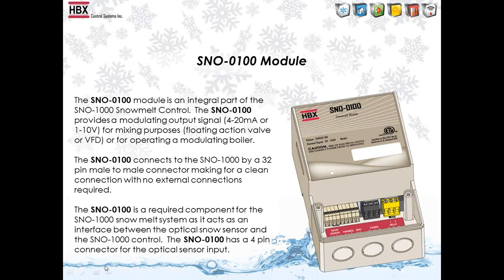So the SNO-1000 needs the Snow-100 module to basically make it into a snow melt system. So the Snow-100 is where we tie our snow sensor into, and our return sensor and our second zone sensor, if we're going to be using that. So it needs to have power on it, obviously, and it has an output on it for a floating action valve as well. So it connects to the SNO-1000 with a 32-pin connector along the side, and it just basically connects straight across, and then you have a full snow melt system.